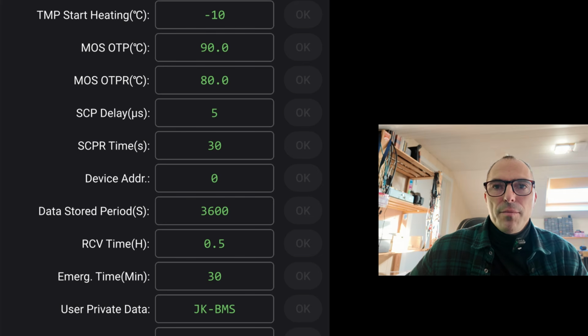When the RCV timer parameter is triggered, you enter the RFV time, the requested float voltage time. The BMS will keep this float voltage for the next 8 hours. It's a parameter you have to set. The RCV and RFV are used when there's communication between the BMS and your charger or inverter via CAN or RS-485. For the moment I don't use this setting. I prefer to keep the cells for a longer time at 3.45 volts. In case of cell unbalance, it gives the balancer some extra time to balance the difference out.